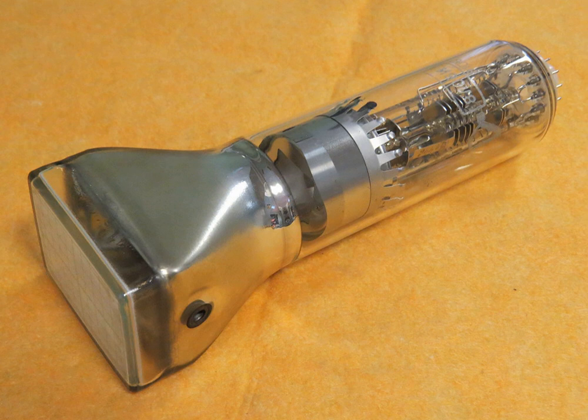These have a large probe body, and some require partly filling a canister surrounding the series resistor with volatile liquid fluorocarbon to displace air. The oscilloscope end has a box with several waveform trimming adjustments. For safety, a barrier disc keeps the user's fingers away from the point being examined. Maximum voltage is in the low tens of kV.